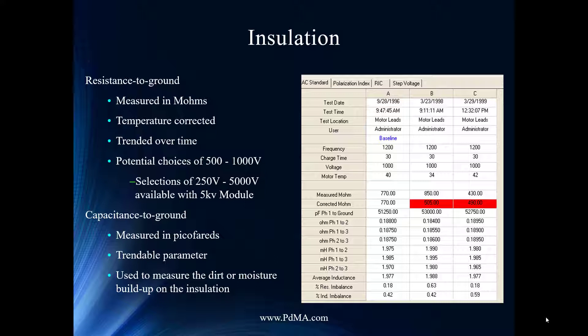Capacitance to ground is a unique measurement not shown by many — but it's a huge benefit to end users because it gives an earlier indication of insulation degradation. Capacitance to ground is measured through a high-frequency AC signal, which passes through insulation contamination far more easily than DC. With AC capacitance you can see the onset of degradation much earlier, and then use the DC resistance to ground as a measure of severity.